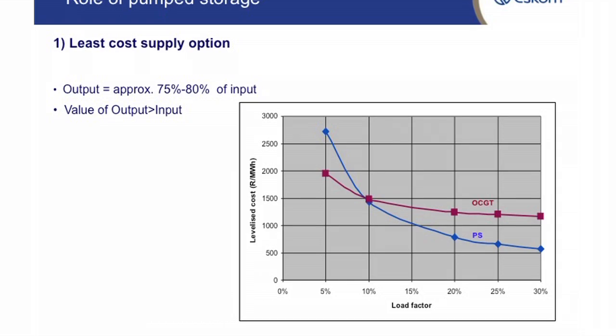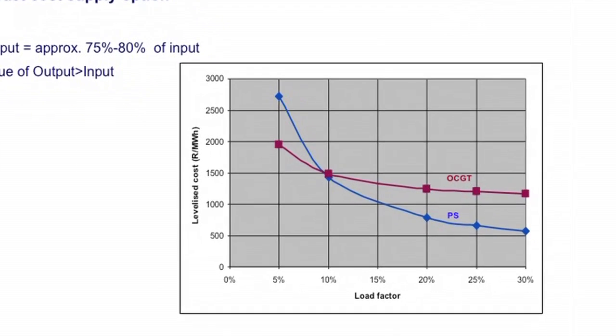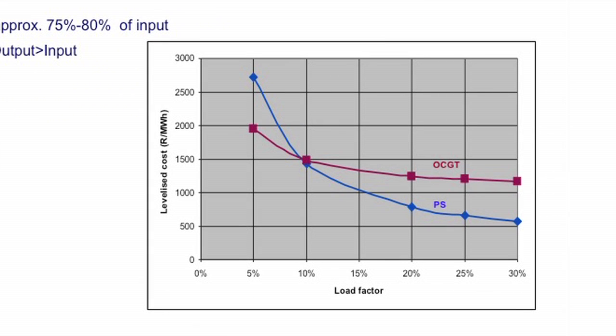If you look at pump storage compared to other systems in our total mix, you'll see that pump storage becomes a viable option if you use it more than 10% of the time, your load factor higher than 10%. Lower than 10%, then OCGT, which is the gas plants, would be more economical.